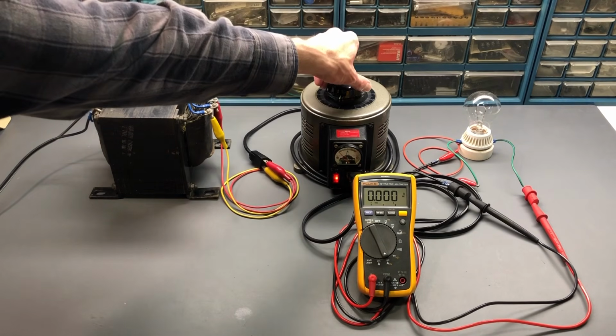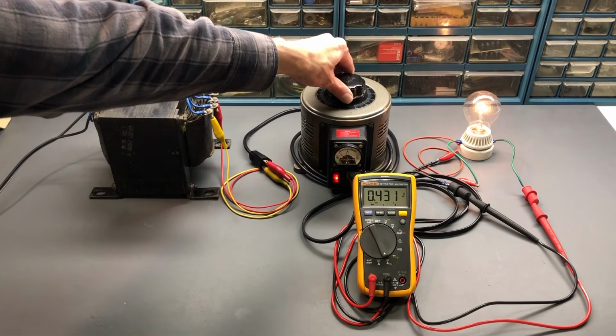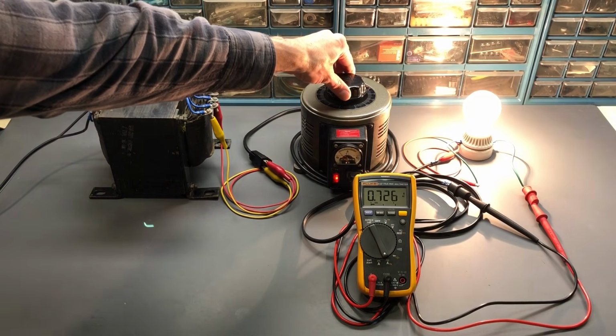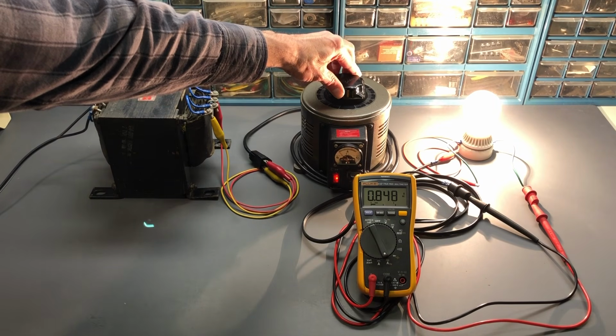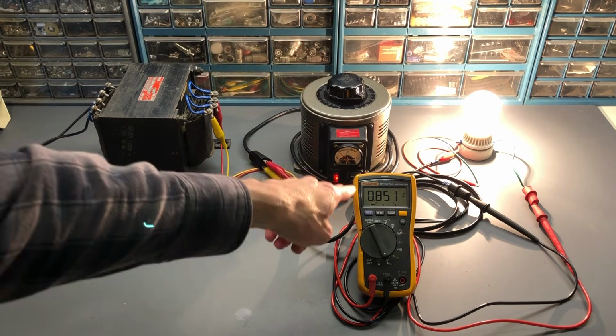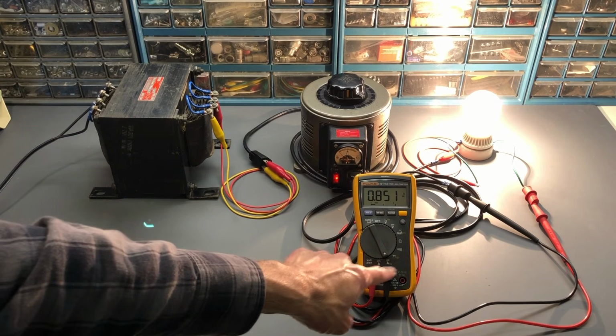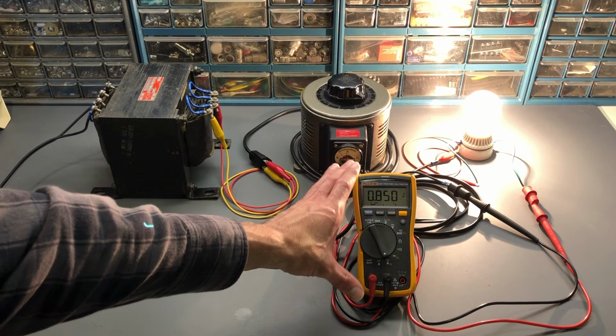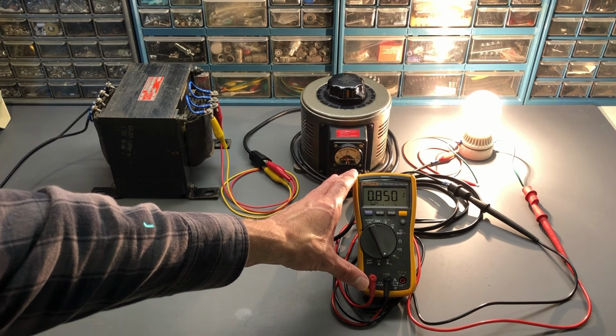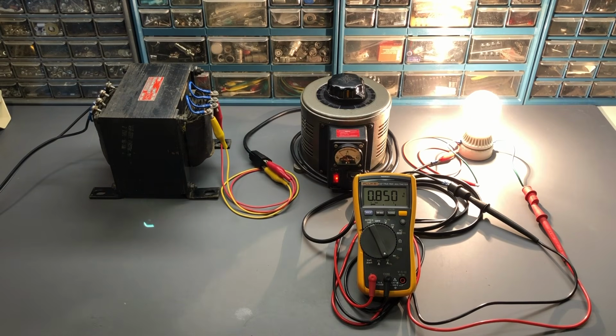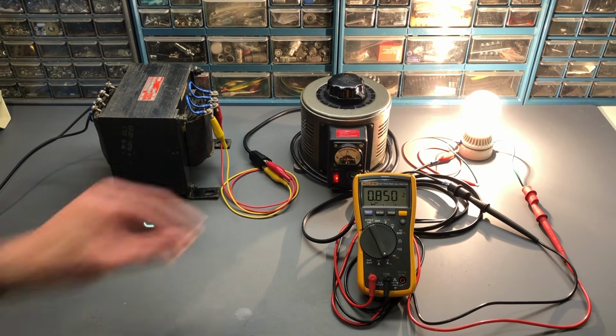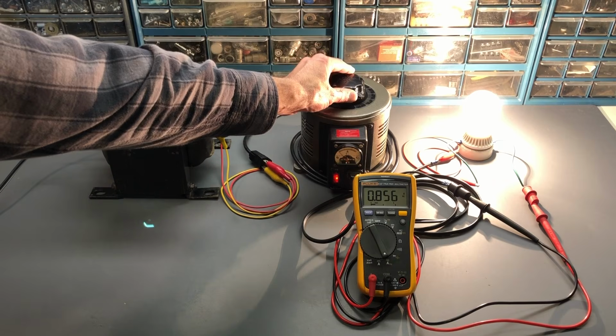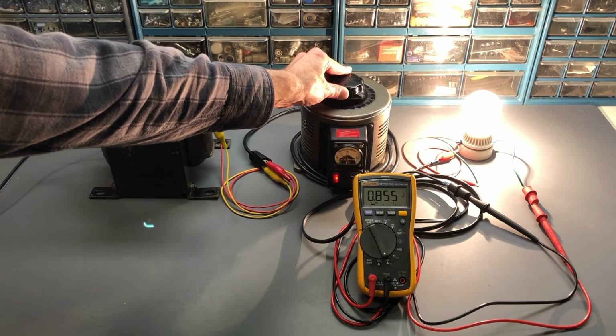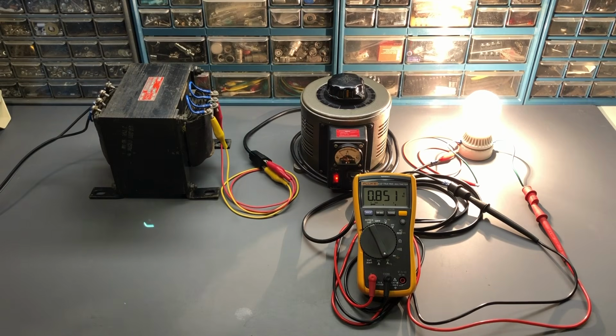So I'll go ahead and increase the Variac. You can see the current rises up very smoothly. The bulb is very bright because, again, we have a short on the output here through that bulb, and it's limiting the current. The device under test is being simulated by this Fluke 117 digital multimeter, just as we've done before. You can see the current, 0.850, so really close to the values that we saw before. That would vary just a little if I bring it up like that. So they're pretty much the same numbers that we've seen before for that current. So again, the current limiting function is working perfectly on this arrangement.